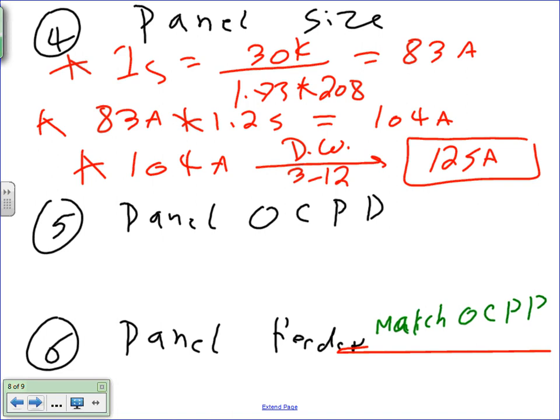That's just the size of the panel. Now, later on, the code says the size of the panel is the size of the overcurrent protection device that protects the panel. But we are engineers, we need to buy the panel first, and then we put the overcurrent protection device. It's up to me to get it. So I size the panel 125.